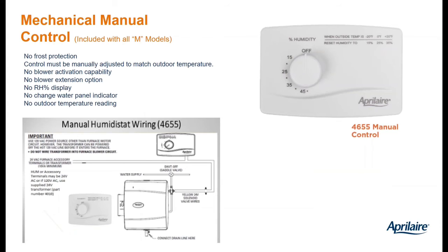If you choose to, instead of installing one of our automatic humidistats, order a model 600M, 700M, 500M, or 400M. The M indicates that the humidifier is bundled with a mechanical humidistat. So, mechanical humidistat, see it pictured there. Obviously, the consumer is going to have to make adjustments to the RH set point based on temperature. Also, the installation becomes a little more challenging because there's no smarts built into the humidistat. It's mechanical. It calls for humidity when the house is too dry.